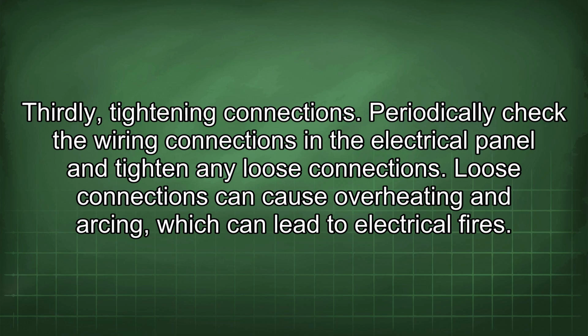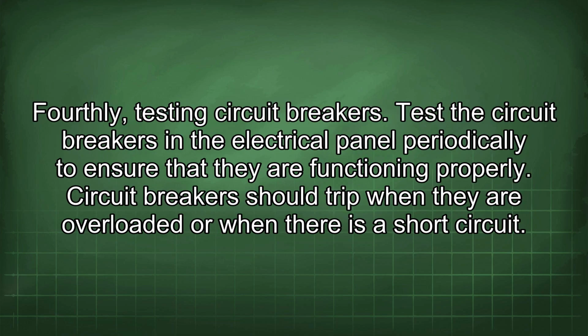Thirdly, tightening connections. Periodically check the wiring connections in the electrical panel and tighten any loose connections. Loose connections can cause overheating and arcing, which can lead to electrical fires. Fourthly, testing circuit breakers. Test the circuit breakers in the electrical panel periodically to ensure that they are functioning properly. Circuit breakers should trip when they are overloaded or when there is a short circuit.